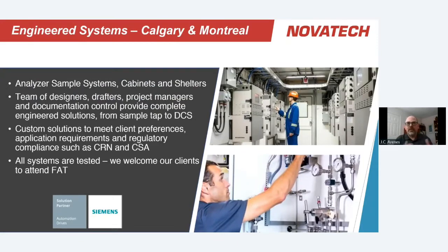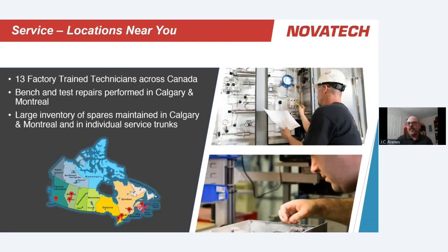In support of the analyzers and manufacturers we represent, we have an extensive engineering team located in our facilities in Montreal and Calgary. It's their role to design and fabricate systems that integrate these analyzers into our clients' processes. Many analyzers are extractive in nature — we have to pull the sample from the process to the analyzer, requiring a sample conditioning system. These analyzers often aren't suited for direct outdoor installation, especially through Canadian winters, so environmental protection may be needed, along with regulatory requirements such as the Canadian Electrical Code, hazardous area certification, and CRN for pressurized systems.